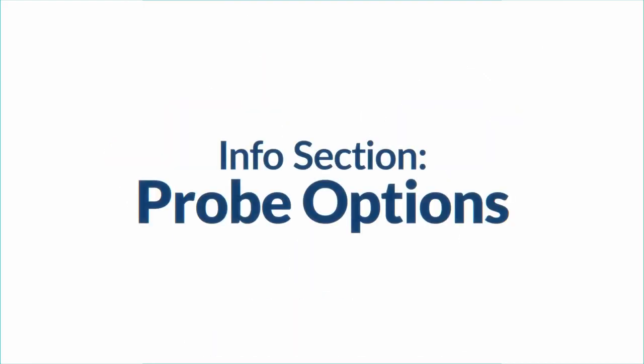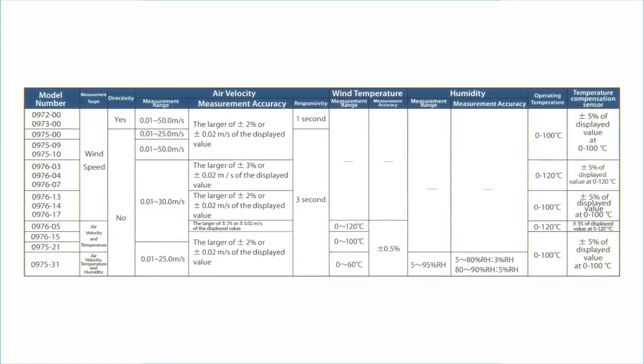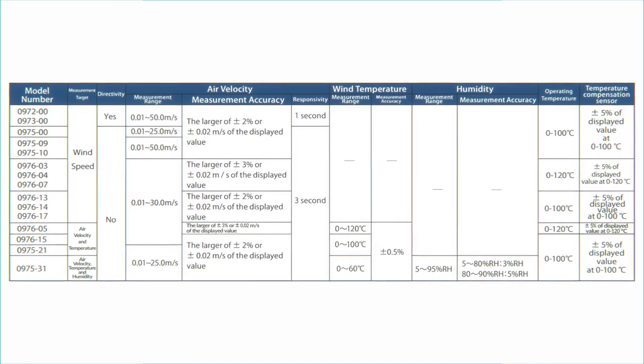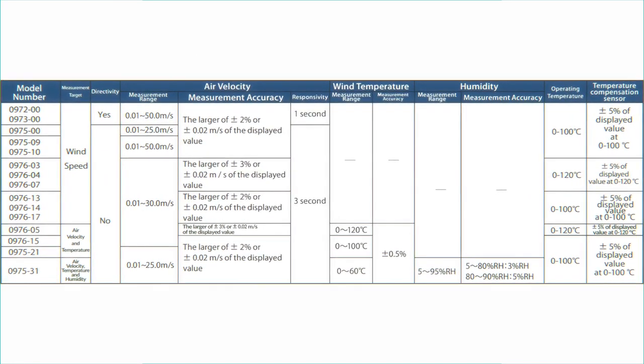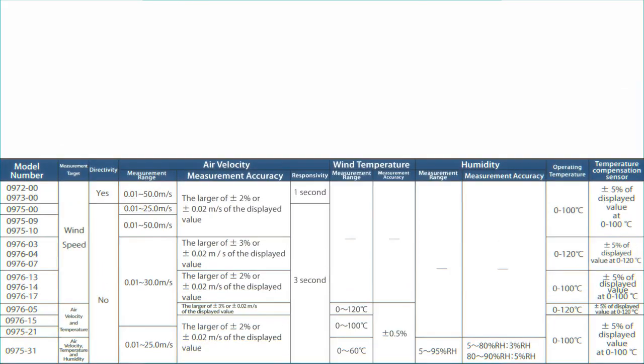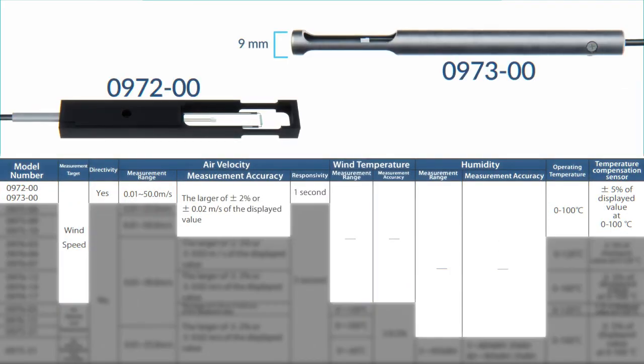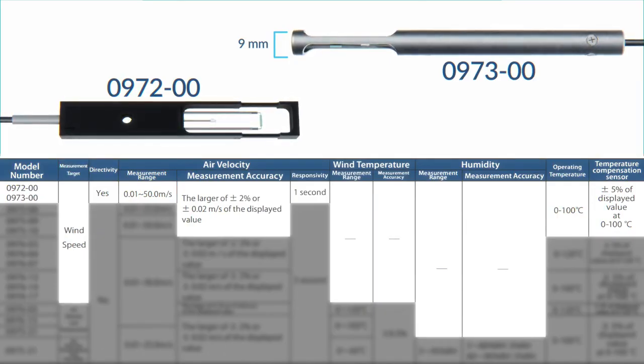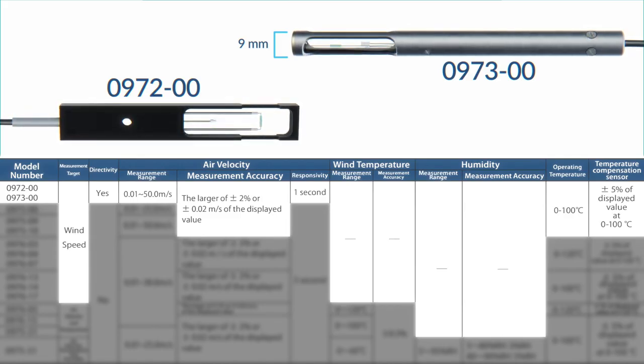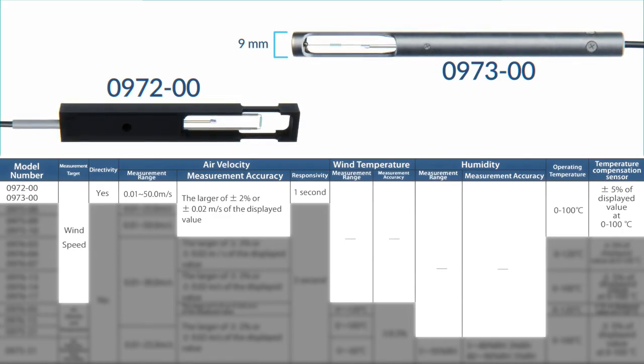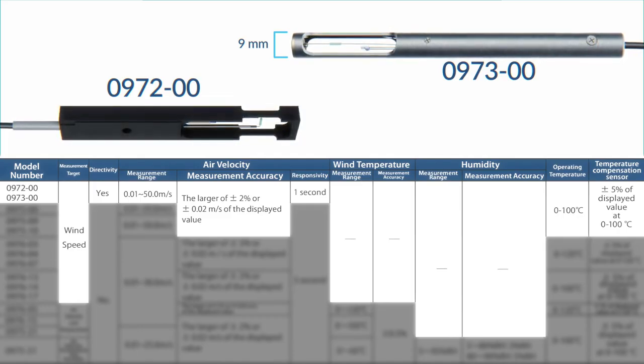These multi-channel anemometer models are compatible with 15 different probes. Each one has its own application where it's best suited. So, in case you're still deciding which one you'll be picking for your order, or if you're just looking for further insight into your selected probes, here's a basic breakdown of each model. Models 0972-00 and 0973-00 are unidirectional probes that measure air velocity within a range of 0.01 to 50.0 meters per second. They're accurate to the larger of plus minus 2% or plus minus 0.02 meters per second of the displayed value, processed every second, and operate at temperatures from 0 to 100 degrees Celsius.